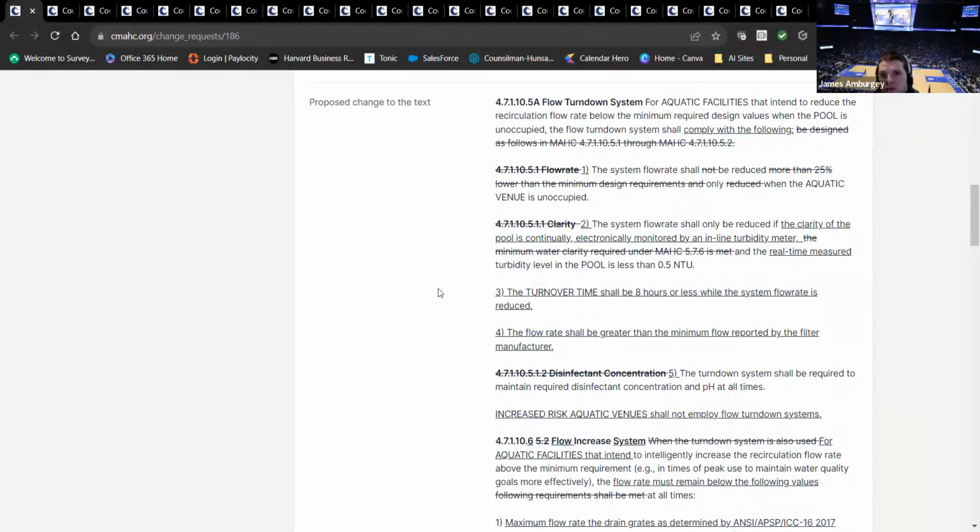Yeah, my concern would be here, if you have a pool with a crappy sand filter and cyanuric acid in it, it's going to take about 7 days to get 3-log crypto removal at the 6-hour turnover level. So if you start allowing that to be 12 hours or 24 hours, you can get into 2 weeks, 4 weeks to get 3-log crypto removal. I think there's a point where you can't allow unlimited turn down.